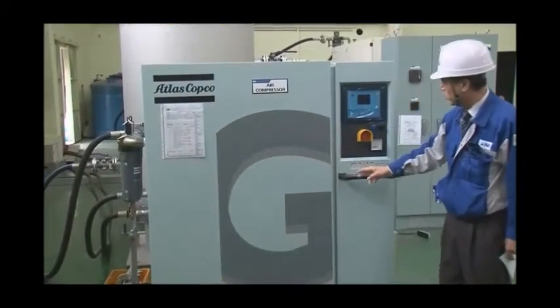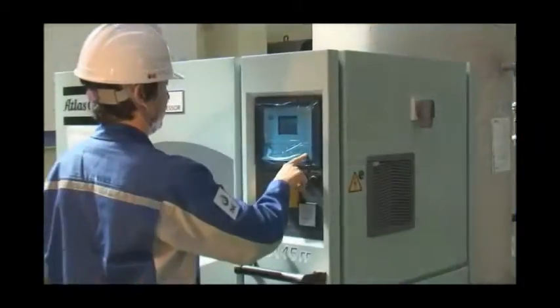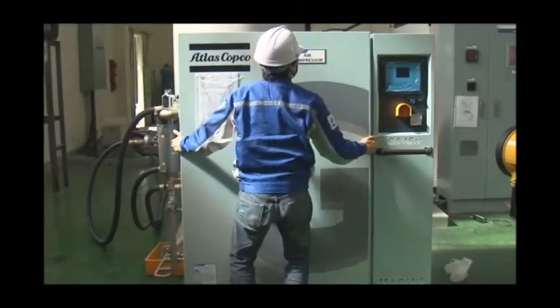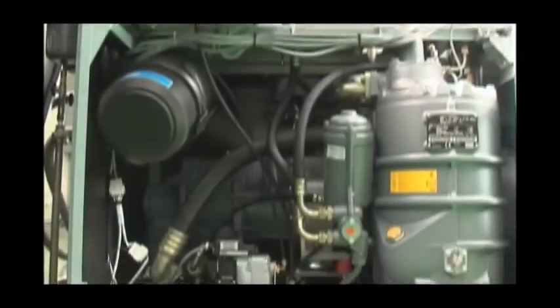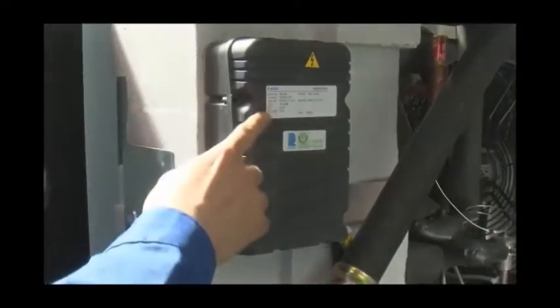Now we introduce individual equipment one by one. This air compressor is a single stage, oil injected screw type compressor, driven by electric motor, and air or water cooling type available, according to the capacity required. This is water cooling type.